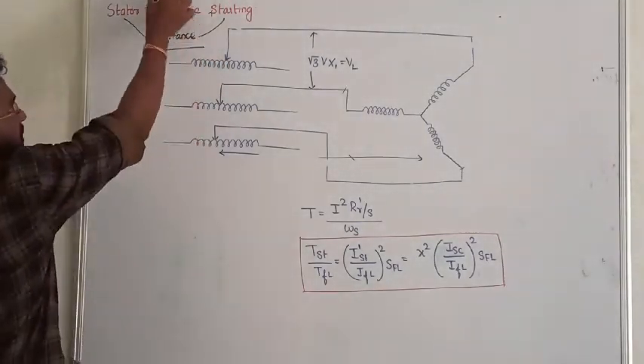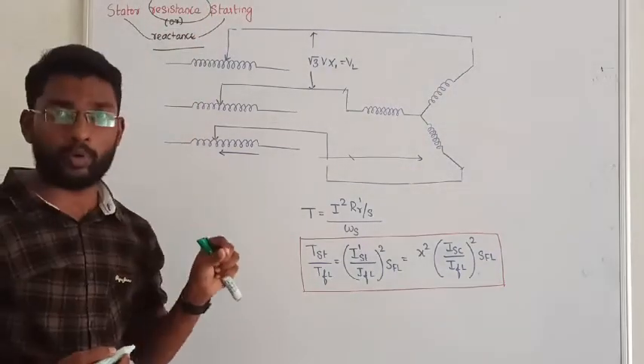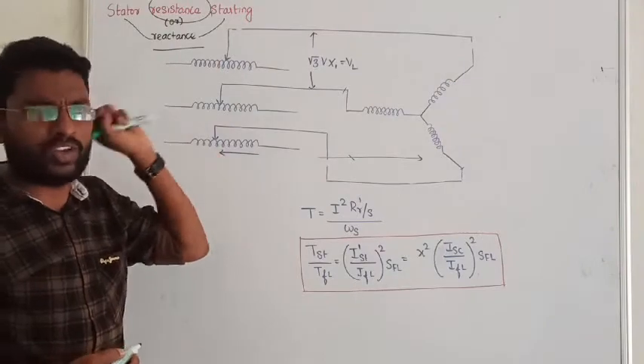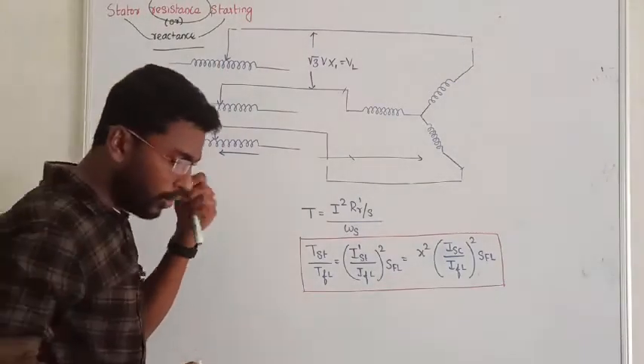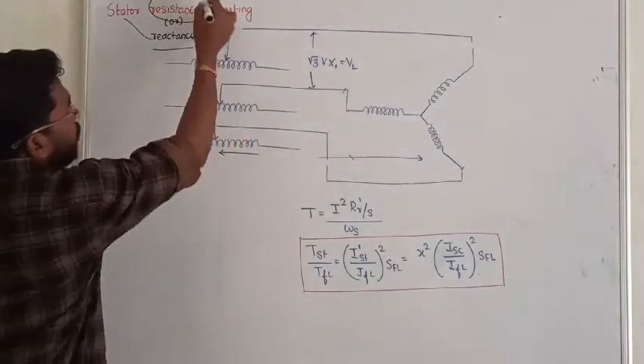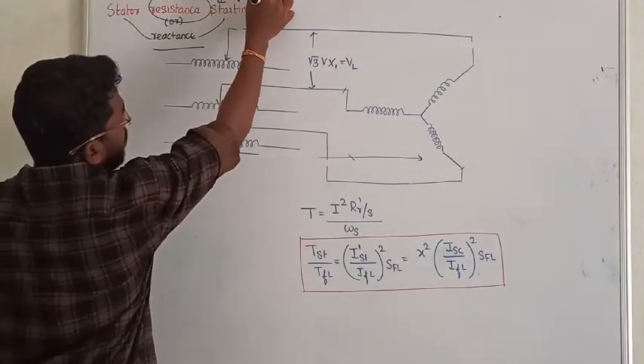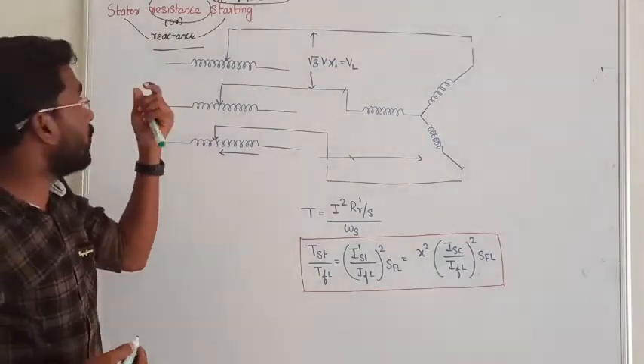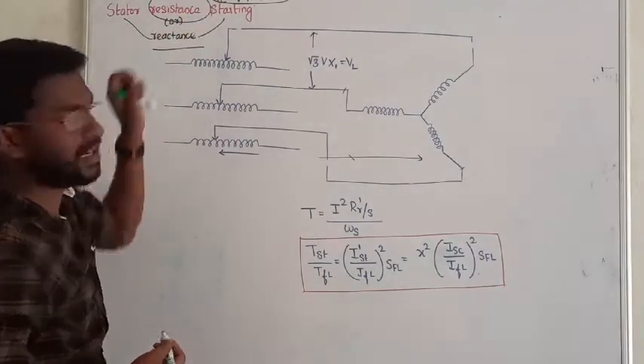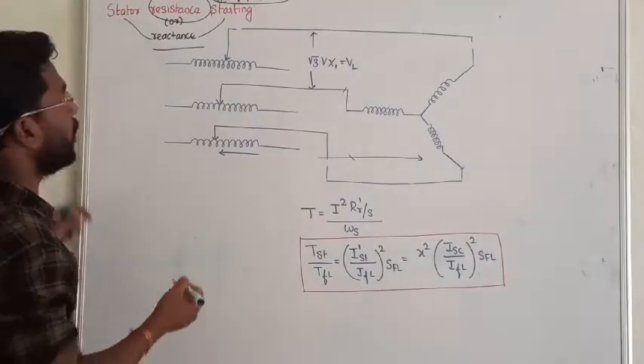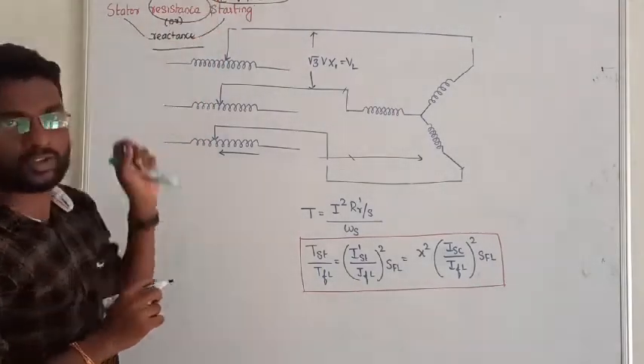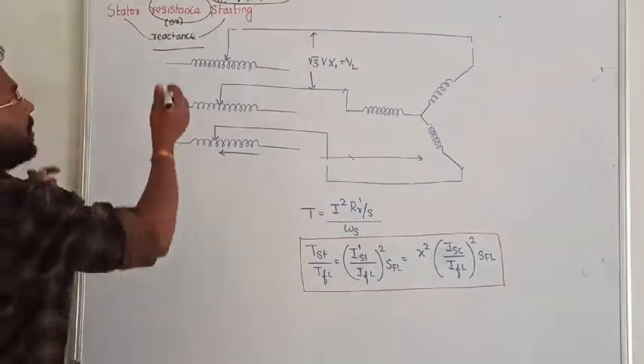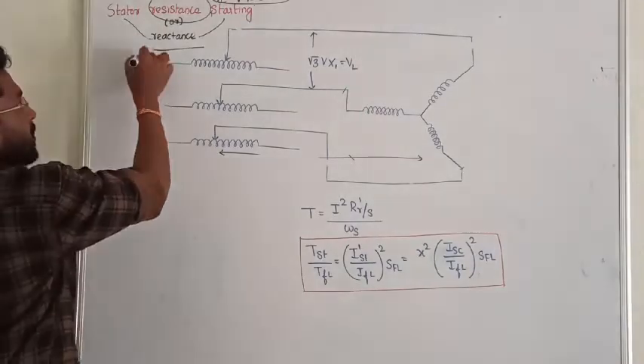By using resistance, we can control voltage and also control the current. But the problem with resistance is we have I²R loss — copper loss. To avoid this copper loss, we go with reactance. The Stator Reactance starting method can reduce the losses. However, compared to resistance, the reactance method is costlier.